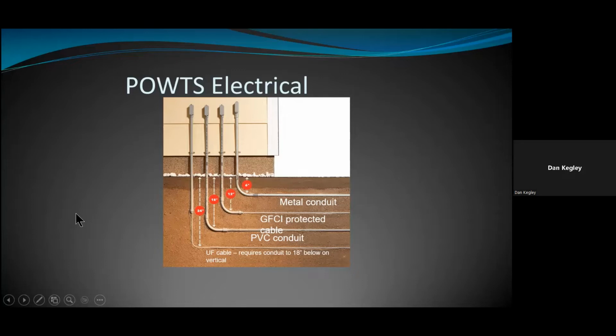direct buried, anything that comes out of the ground, because we have frost up here in the northern parts of Wisconsin, that frost heaving can actually take a conduit that's in contact with the earth and basically shove it up into whatever it's fixed to, like a building or a post, and those kinds of things. And so the code requires a compensation for that.